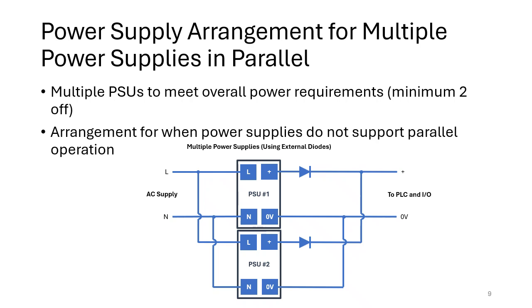Now, if the power supplies don't support parallel operation, then you can add those diodes externally. And it's a very simple circuit. It's just a forward bias diode from the positive output of each power supply, and then they're wired together to the same positive to the actual PLC or I/O. So again, simple supply arrangement, single supply coming into two power supplies paralleled up, but with that additional diode on the output of the power supplies. So that's an arrangement for when power supplies do not support that parallel operation. Now, some power supplies have that diode built in, so you don't need that. The other option is, as I said, to use that redundant supply arrangement where we use that redundancy module.